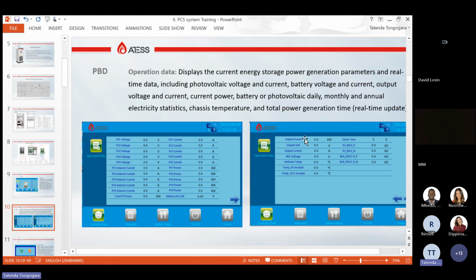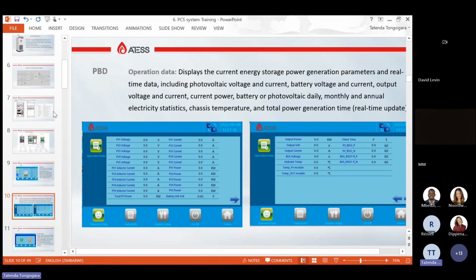So on the second page of our data, you see your output power, your ambient temperature, module. So if you are designing your system in a container, it's best you separate the battery and the inverters. So for these inverters, you can put your extraction fans and everything. And then on the battery side, you can put your aircon. The reason why we don't advise clients to put aircon on the HPS PCS side is because we don't want moisture to start forming on the control boards, because it will damage the control board. So if you put just extraction fans and ducts, you design your duct and extraction fan, it will be good enough for the cooling of the system. But on the battery side, you can put your AC.